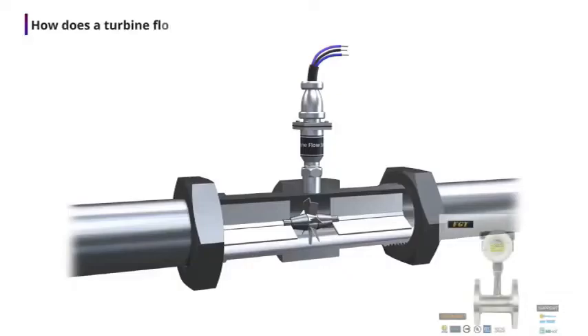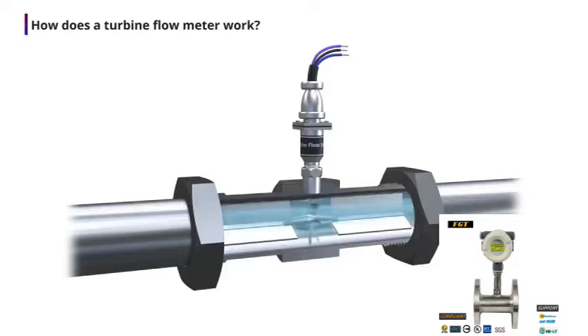First of all, let's talk about how a turbine flow meter works. A turbine flow meter is inserted in a pipe directly in the flow path. The mechanical part of the turbine flow meter has a turbine rotor placed in the path of a flowing stream. The only moving part of the turbine meter is the mechanical rotor. The rotational speed of the rotor depends upon the flow velocity.